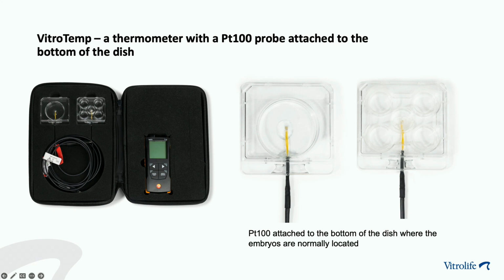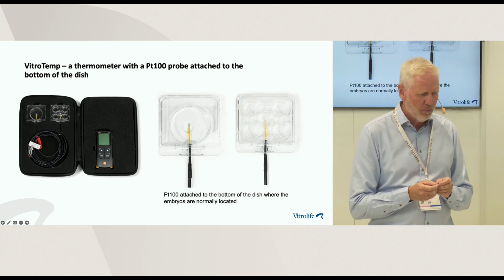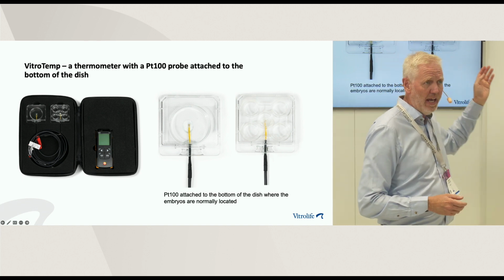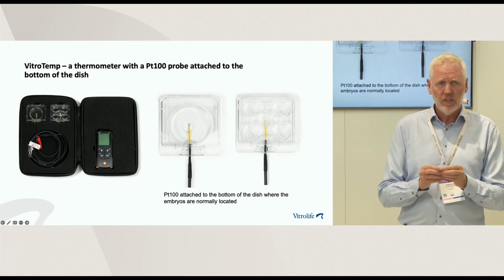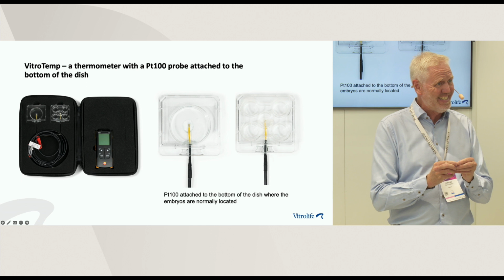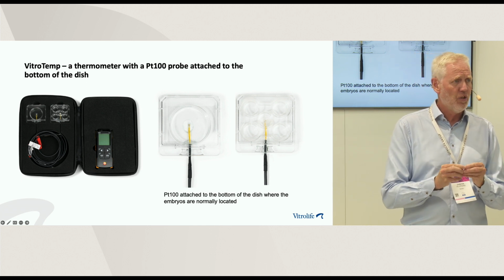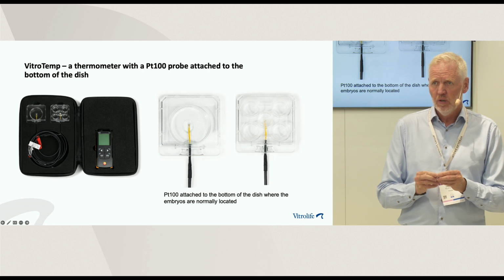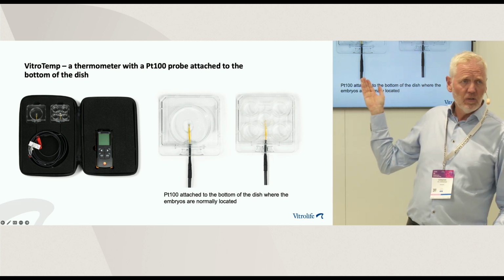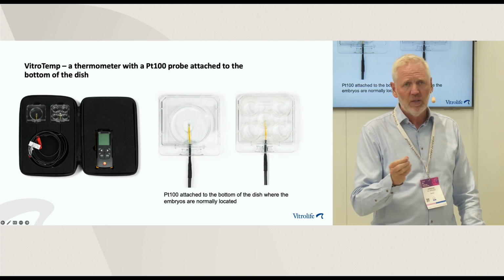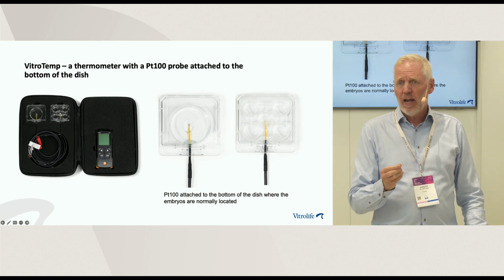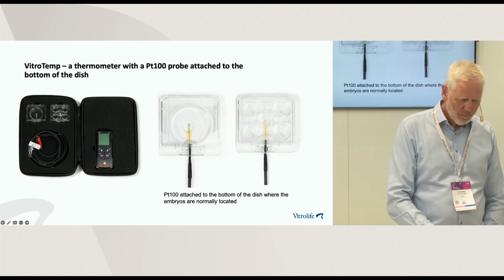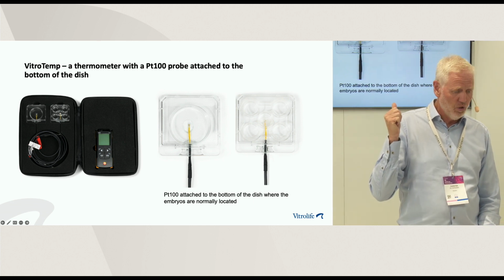The temperature measurement with VitroTemp is a completely different method. It's based on a temperature-dependent resistance in a platinum plate called PT100, which is attached to the bottom of the dish. So the dish design ensures that you will exclusively measure the temperature where this platinum plate is, with far less thermal conductivity interference. Furthermore, by measuring with this, there are no handheld steps that could further interfere and cause errors and inconsistency. This makes this measurement very easy to use.